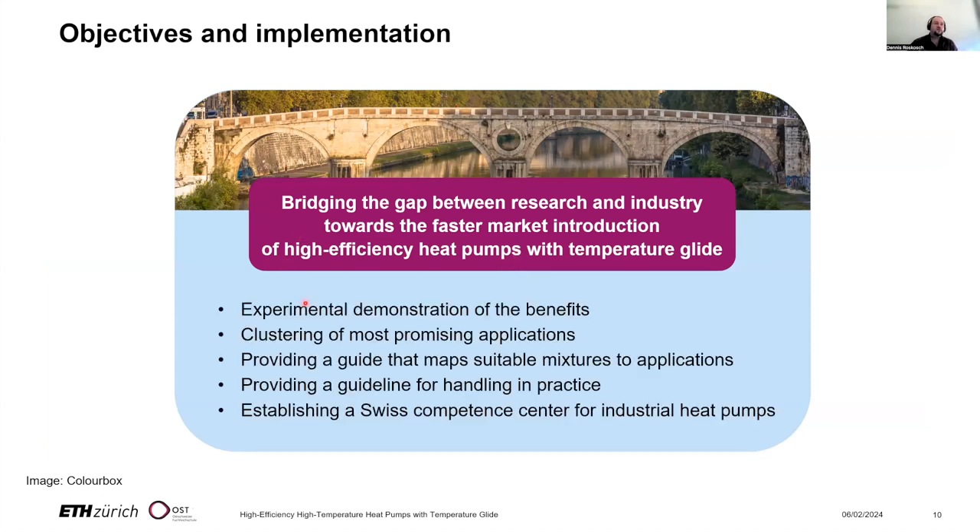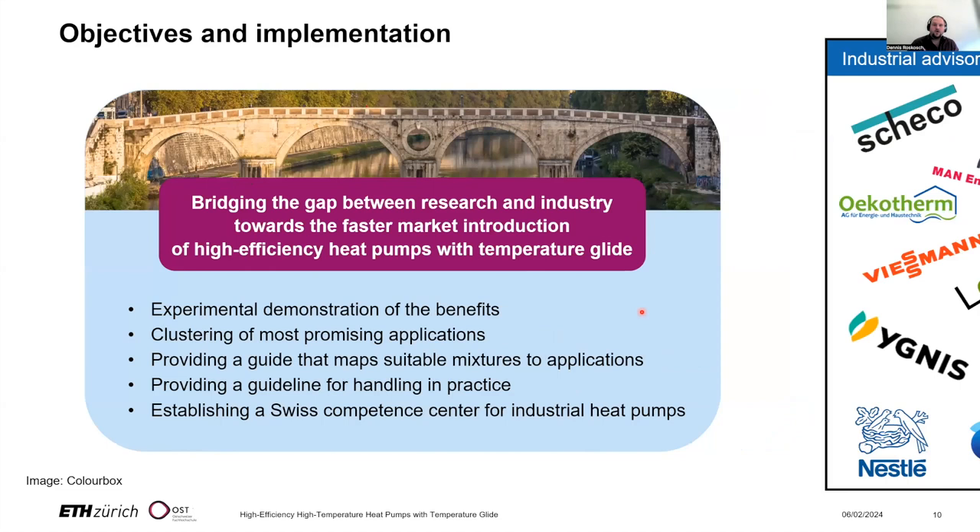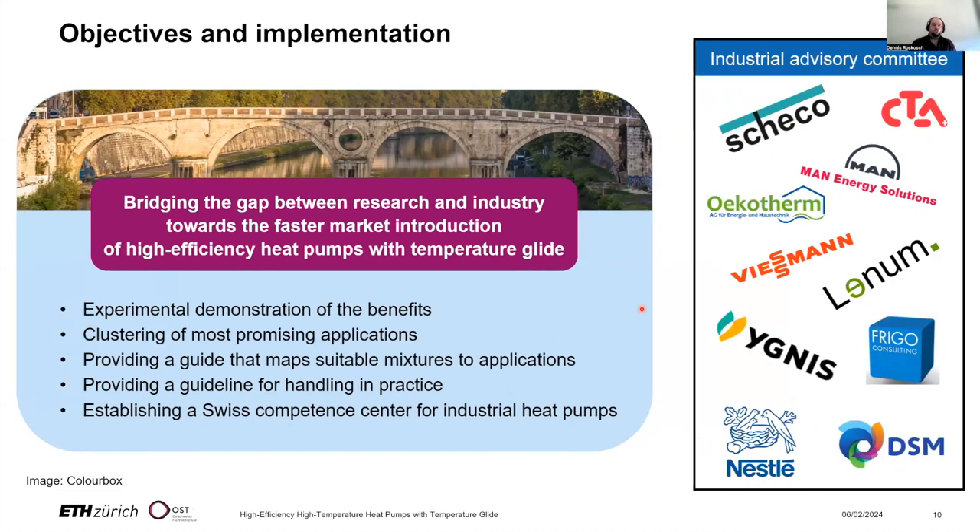This includes experimental demonstration of the benefits, clustering of the most promising applications, and providing a guide that maps suitable mixtures to applications. We also address practical handling of mixtures — for example, if there is a leakage and refrigerant is lost, we need to know the current composition inside the heat pump before refilling. We also establish a Swiss Competence Center for Industrial Heat Pumps. To bridge the gap and gain industry insights, we have a prominent industrial advisory board comprising partners along the entire value chain from manufacturers to planners to users.